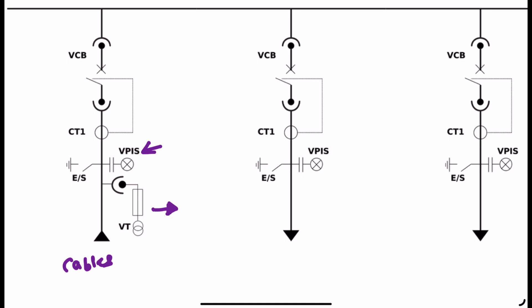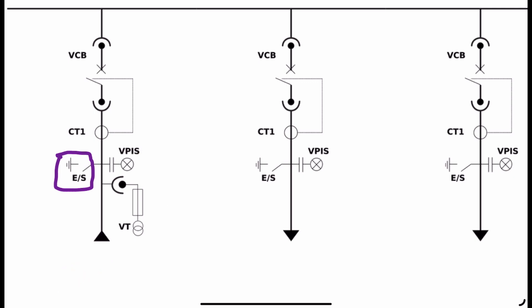Indicator lights will glow if there is supply present. Parallel to that, an earth switch is also provided — this is a safety feature. The earth switch helps us ground any trapped charges on the cables. So any trapped charges are grounded through this earth switch, providing additional safety. That is the earth switch used alongside the Voltage Presence Indication System.